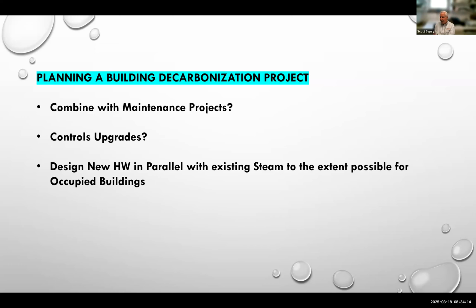Can you combine your project with maintenance projects? If you need to replace a coil in an air handler that's 30 years old, then you probably want to replace the entire air unit. You may plan partial or phased building conversions with the maintenance as the driving project. You can build out low temperature hot water equipment over time while you continue to use a steam-based high temperature water system, maybe 160 or 180. The last piece of the system then might be the arrival of central hot water piping or the installation of a new low temperature heat pump within the building.